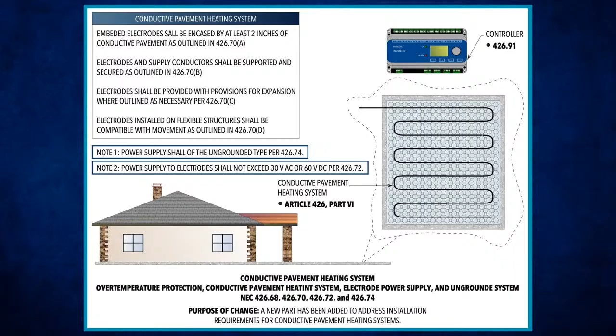That's interesting, because when it talks about those electrodes and supply conductors within that conductive pavement, it literally tells you they're required to be supported and secured by some type of non-metallic means. That's what we did. We put non-metallic chairs in there. Did y'all take into consideration any expansion or contraction? Yeah, whatever they told us to do on the install, we did the best we could. It's hard when they're just pouring concrete on top of them, and those concrete guys do not care.